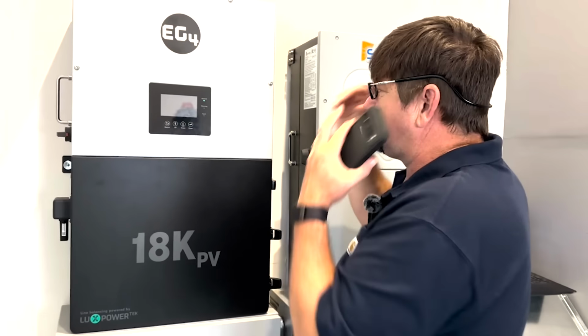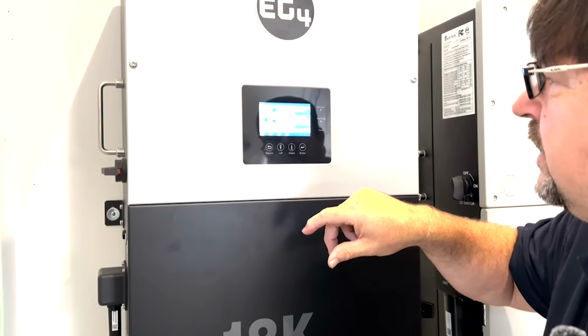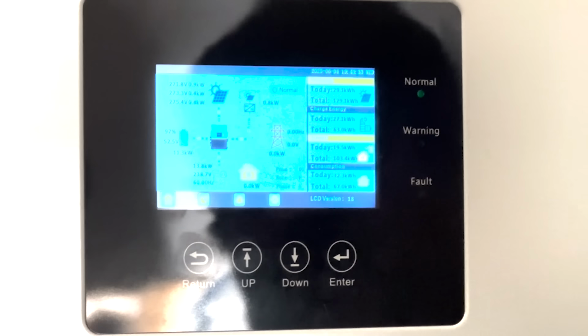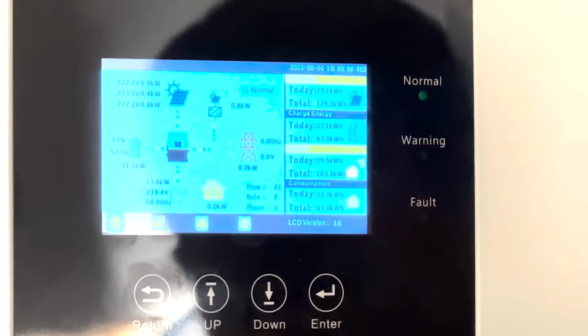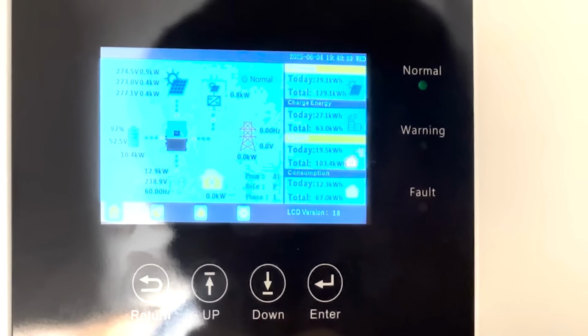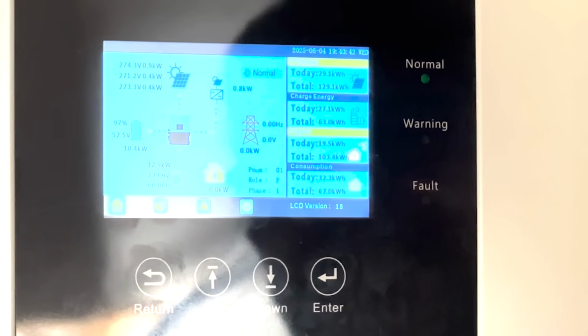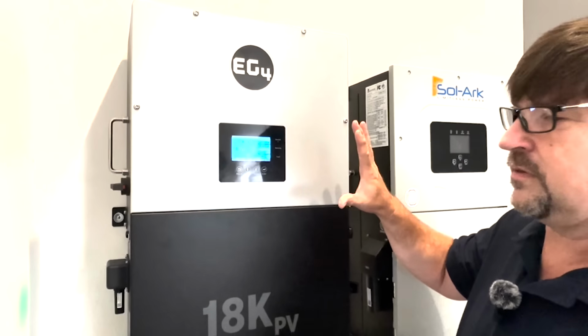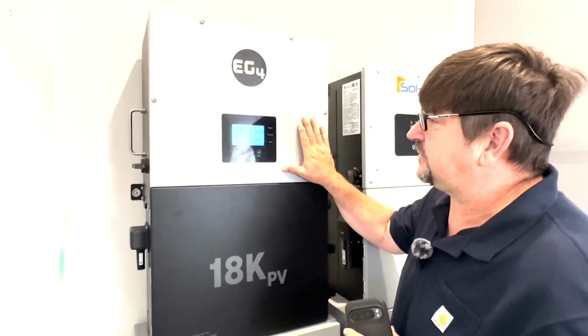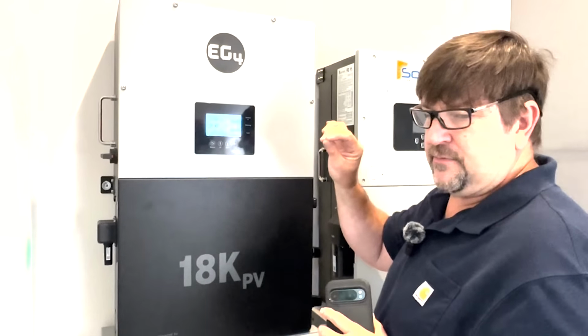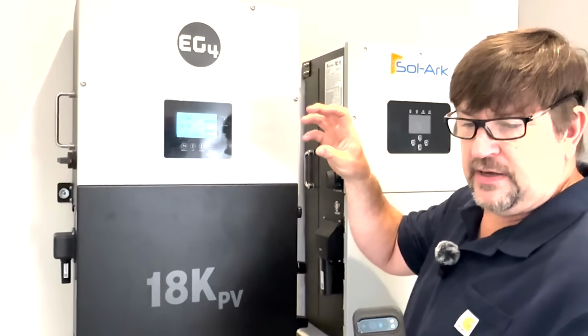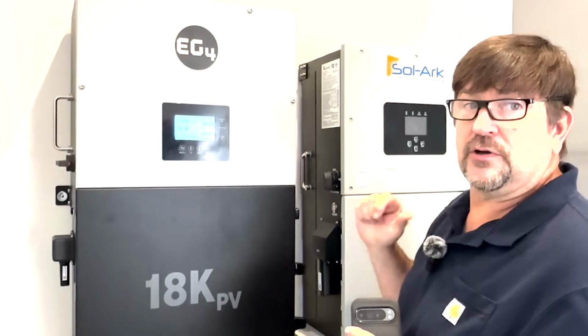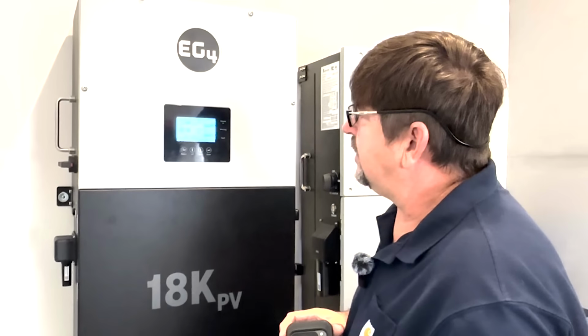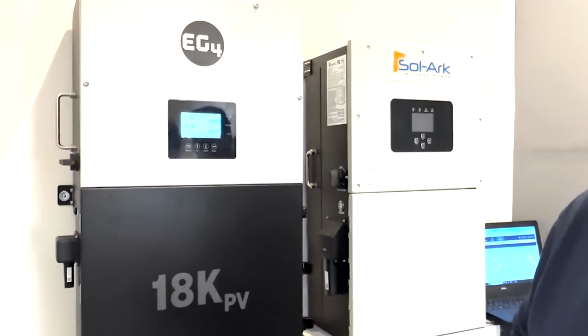Okay, so it hasn't shut down yet, which is cool. We're running 13.8 kilowatts. Now we are AC coupled and DC coupled, so we're running off of 10 coming out of the battery. It's holding. I think the AC coupling is really helping us. But we're running at 12.9, so we're running over what the spec sheet says this does, which is 12K. I think it runs like 14K with PV for 5 minutes, and I'd have to look at the spec sheet to be exact on that. So it's running over its nameplate, but let's look at the spec sheet.